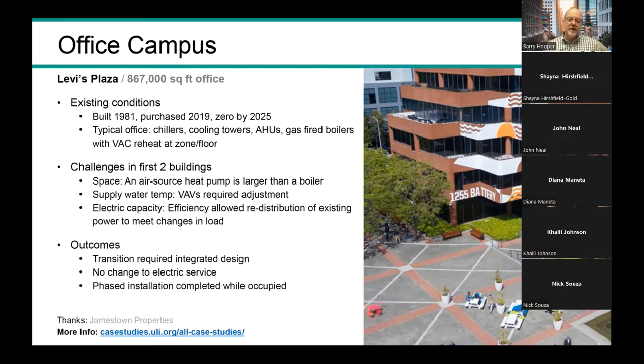The supply water temperature is a common issue — boilers are generally readily able to provide 180 degree hot water, and often designs are built around that. This required a rethink, since with heat pumps — and we'll talk about this a bit more — it's not necessarily the best strategy to try to replicate that same water temperature.